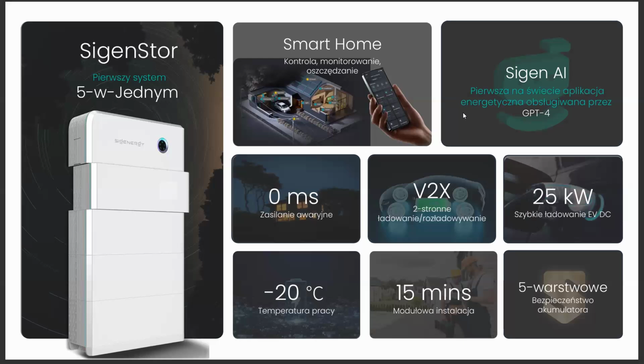Smart algorithms and cost savings, SG-ready. Our system includes built-in SG-ready functionality, with 2 potential free control outputs. This enables direct control of a heat pump and, for example, an additional contactor, creating strong opportunities for energy price arbitrage. Example, some users configure the system so that when electricity prices go negative, pool pumps or buffer tank heating turn on automatically. The system ensures energy is consumed when it is most cost-effective. Most importantly, all of this works without any external control boxes. Everything is managed directly within the MySigen app.